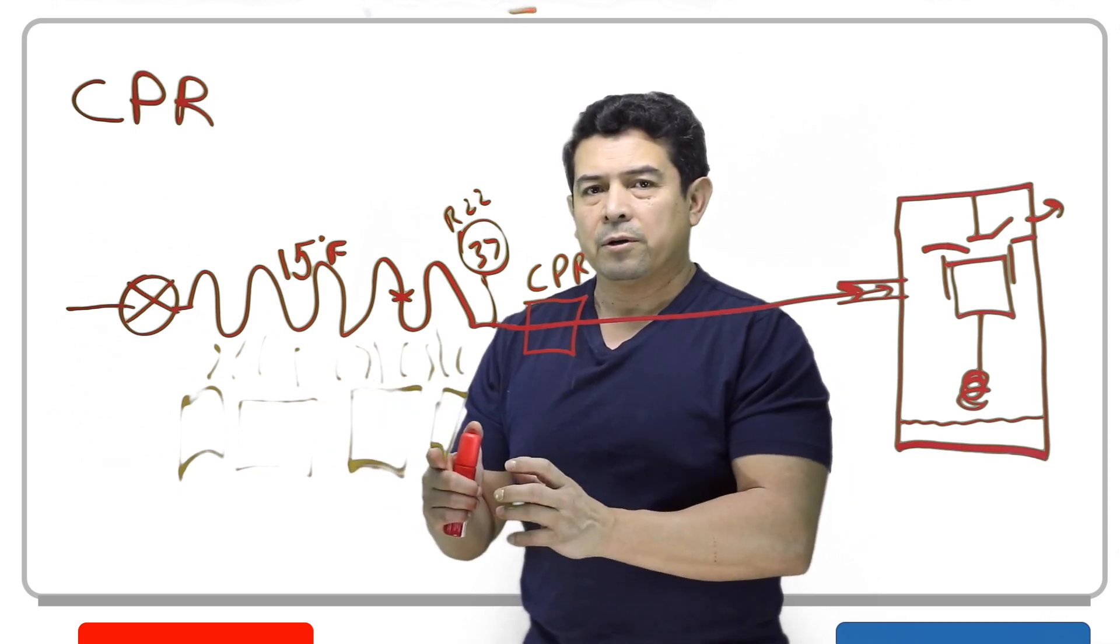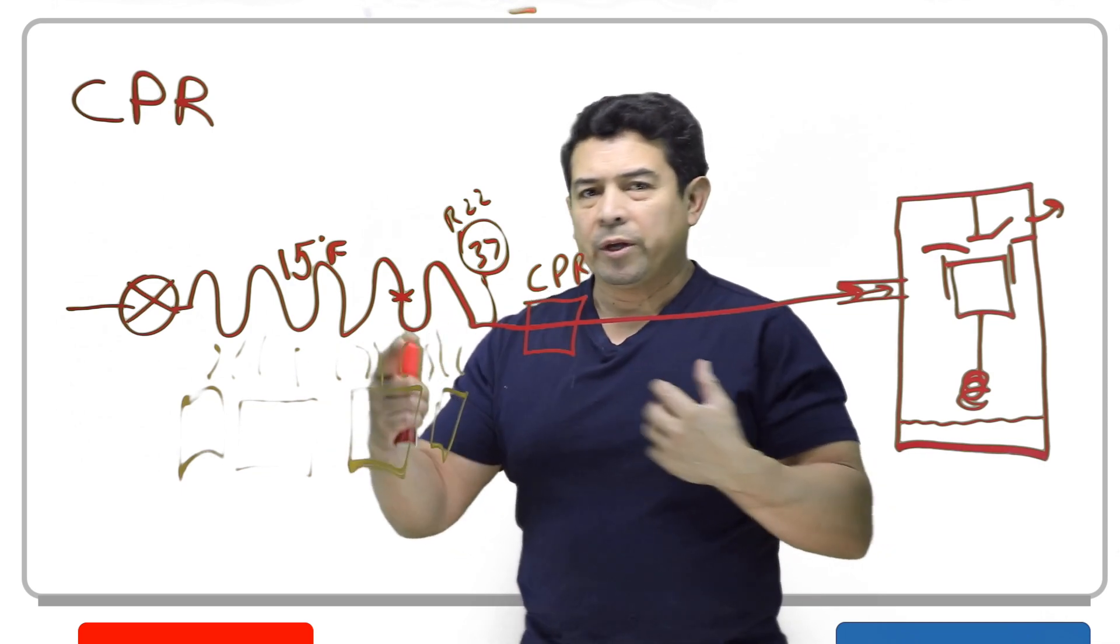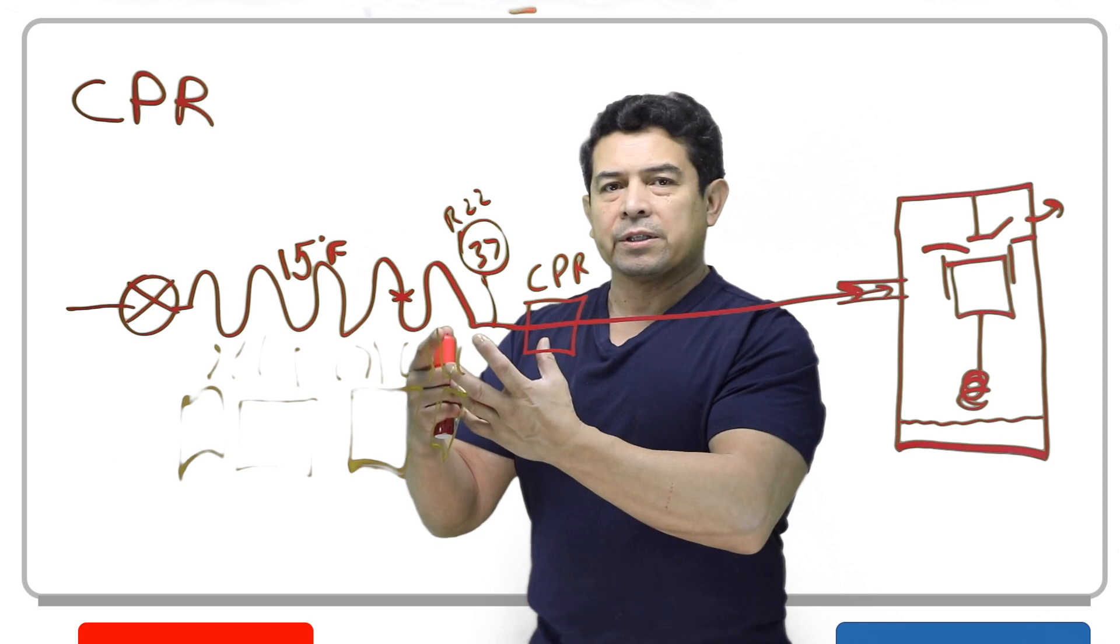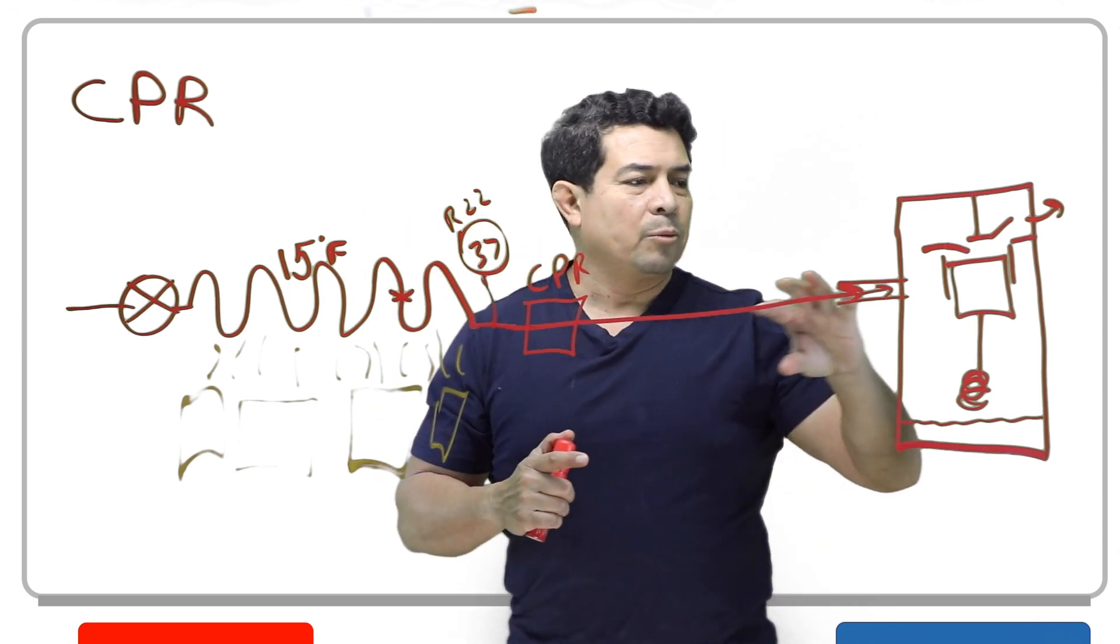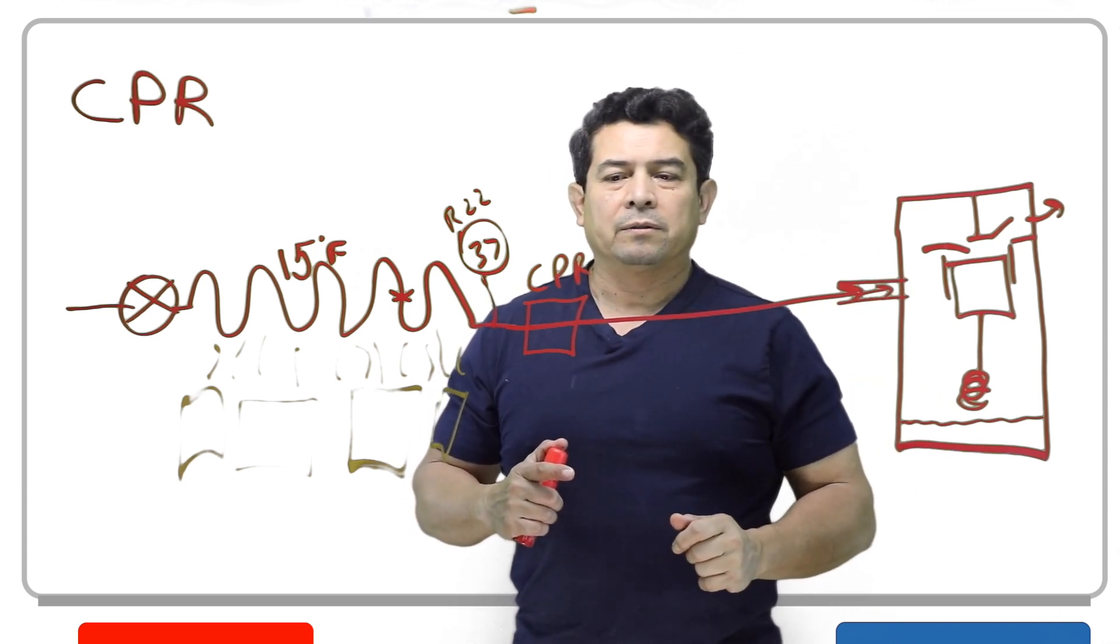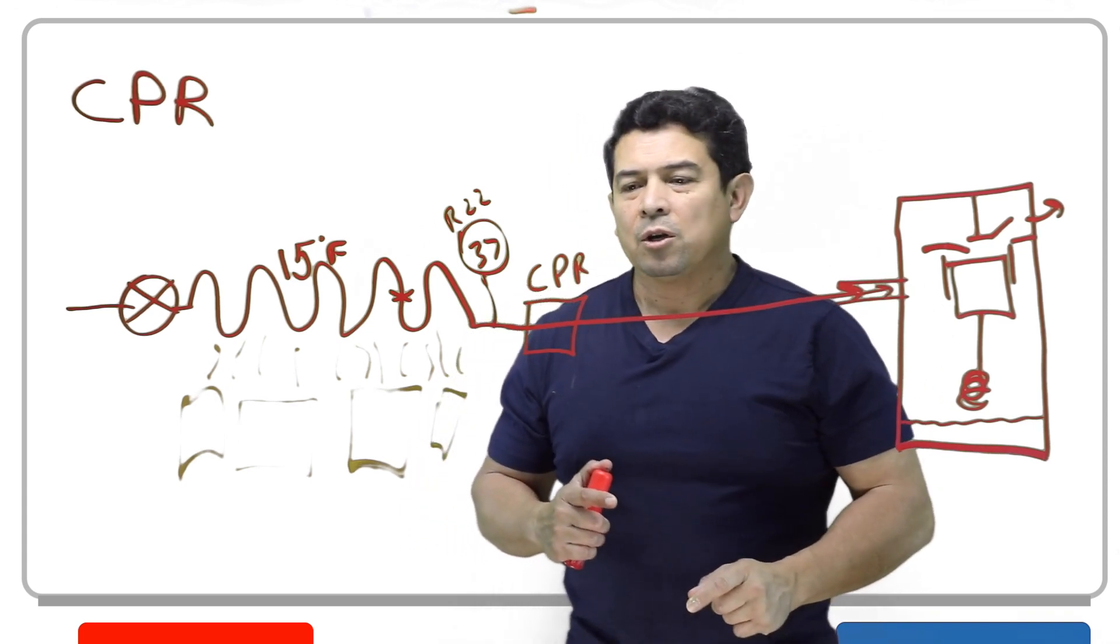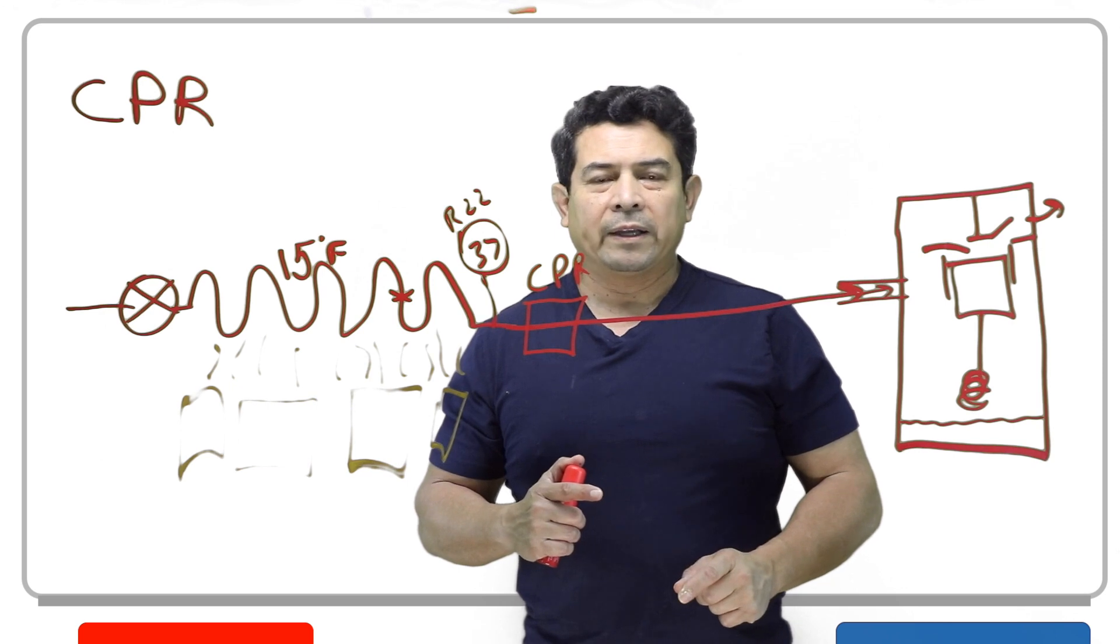This crankcase pressure regulating valve is going to keep that from happening. Once you put food in here, or you leave the door open, or for whatever reason, the load increases, the pressure will build up. This is going to make sure that the compressor is not overloaded. That's the purpose of your crankcase pressure regulating valve.